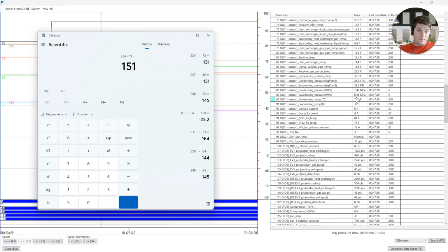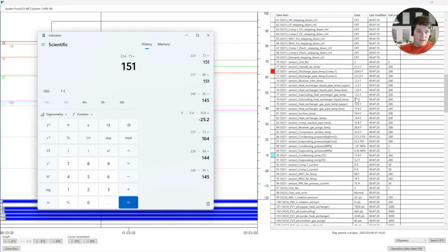151 degrees, right? Wow, that is high. And that's the smaller one. So let's go to the 237 minus 73. 164 degrees. This is over 200%. 200% of what your normal discharge superheat should be.